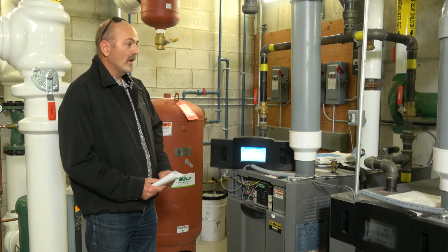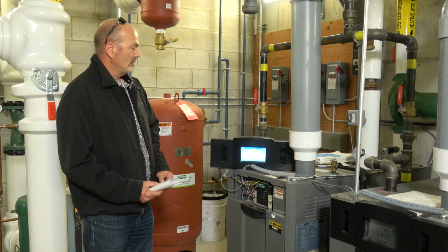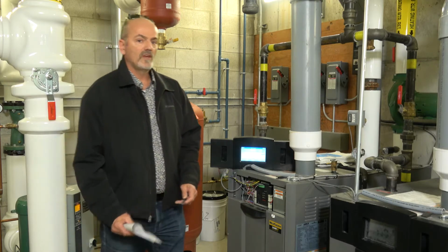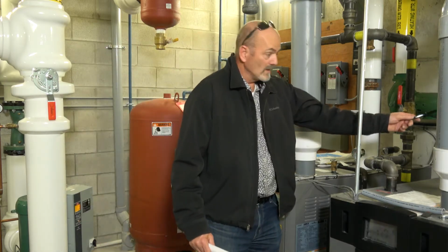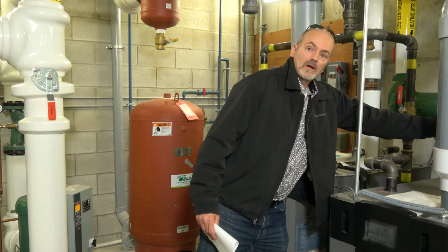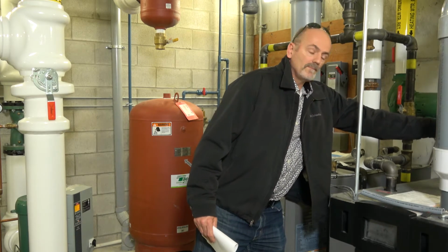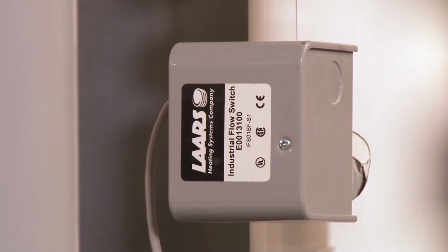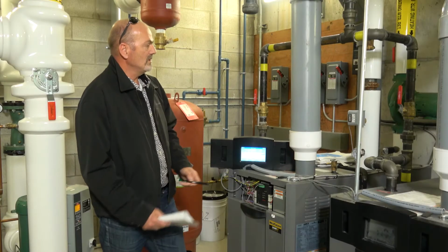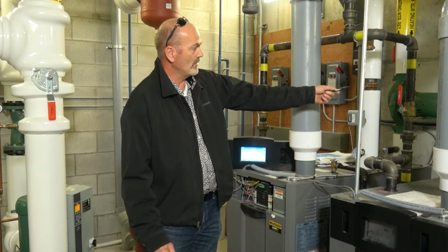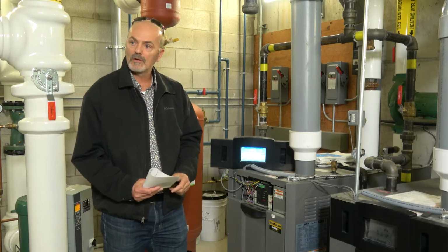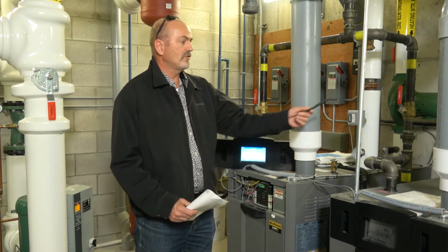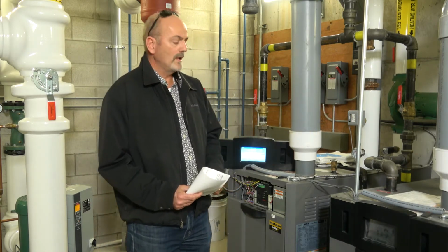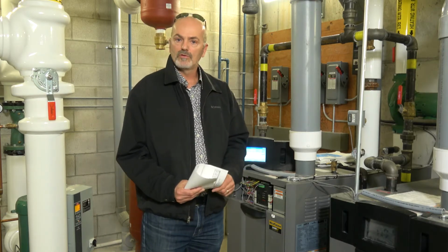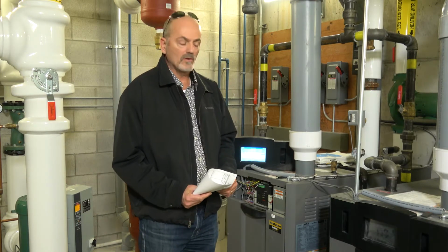As far as the operation of the boiler, there are various safeties. This safety here is a low water flow switch. This flow switch is on each of the 2 boilers. If for any reason the boiler circulators are not functioning or fail to come on a call for heat, then that flow switch will not register flow, and it will not allow the boiler to go through its pre-ignition cycle.